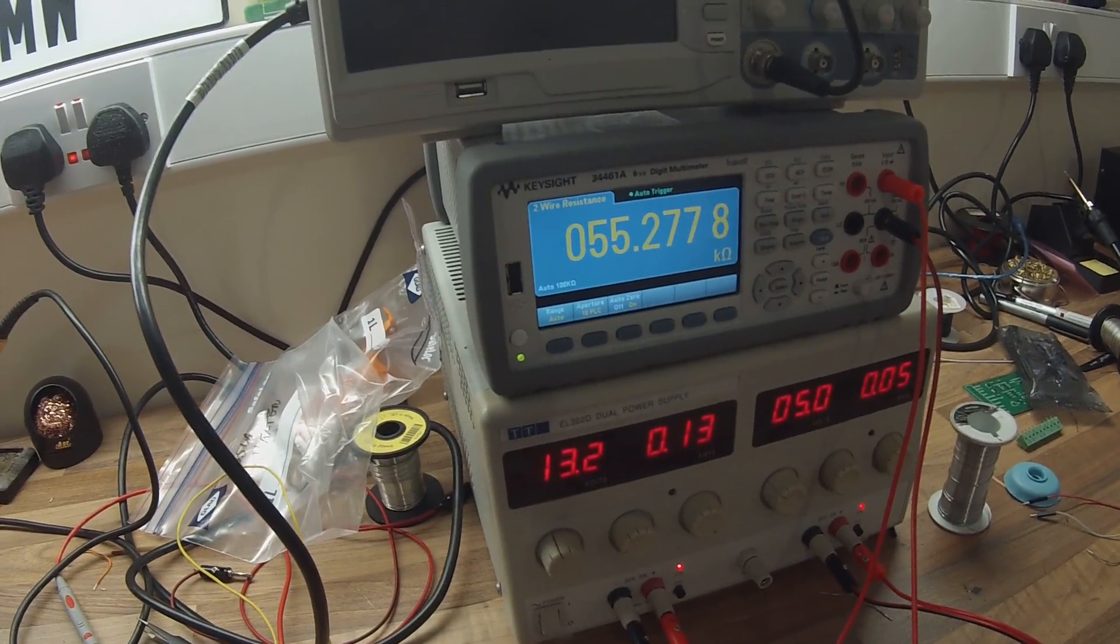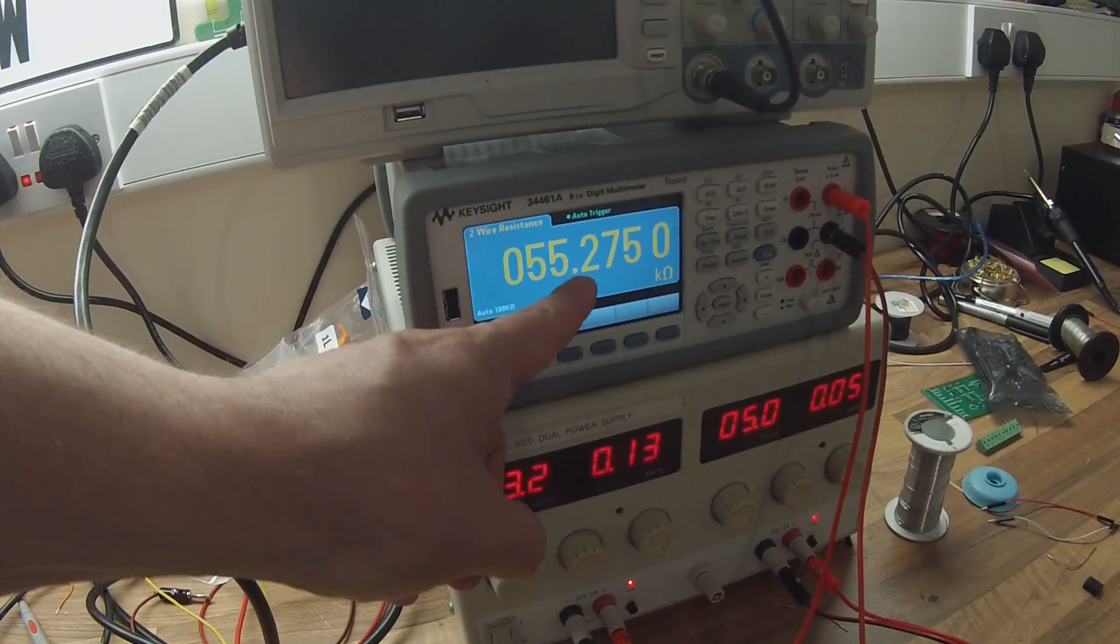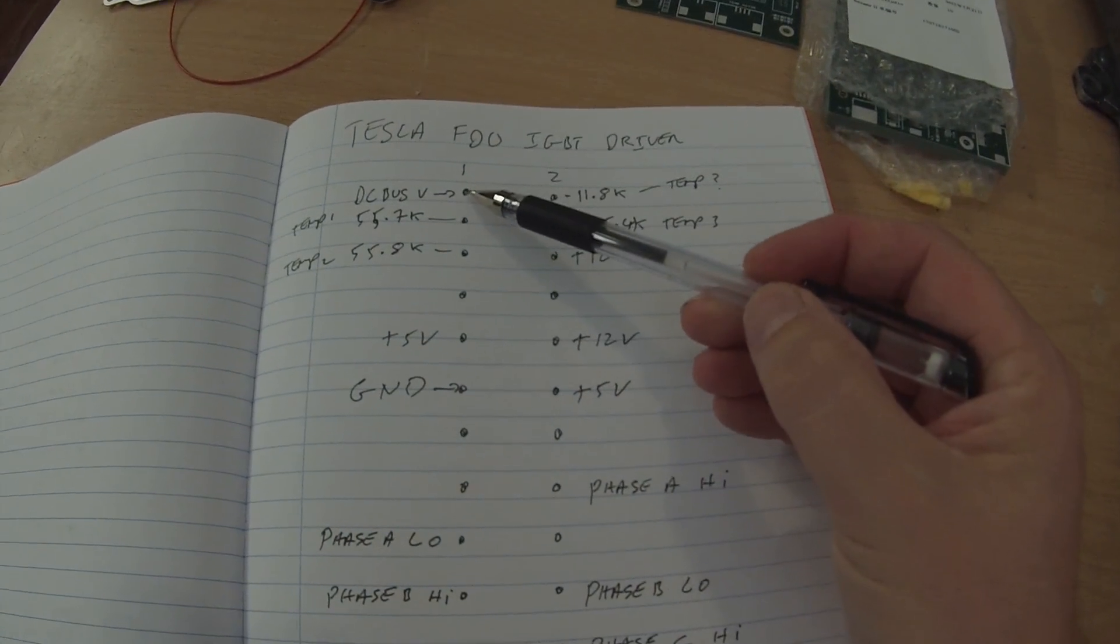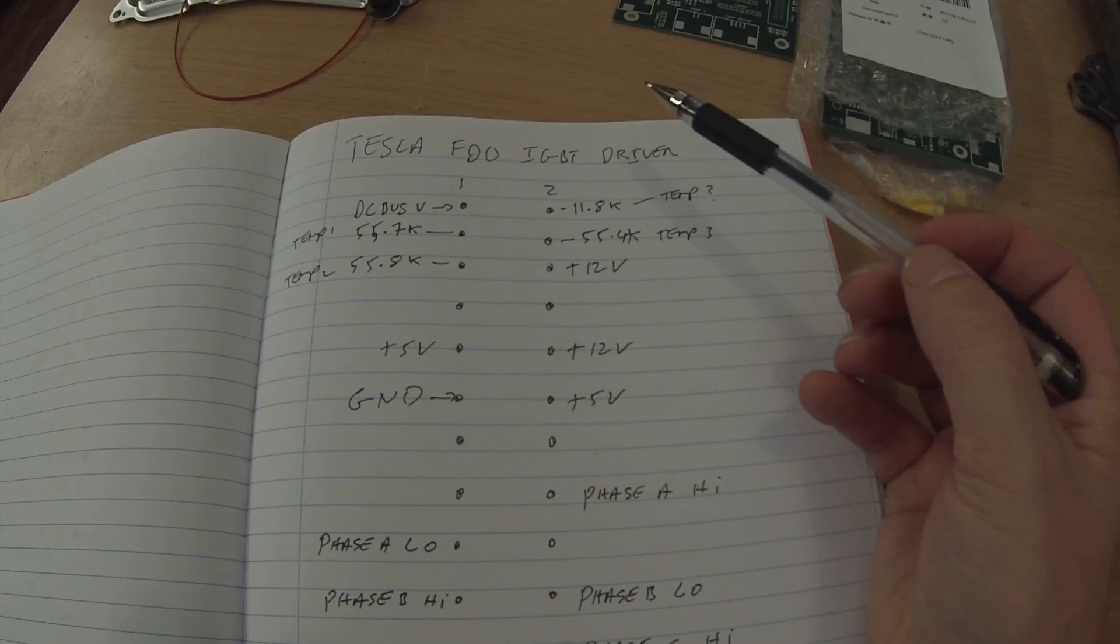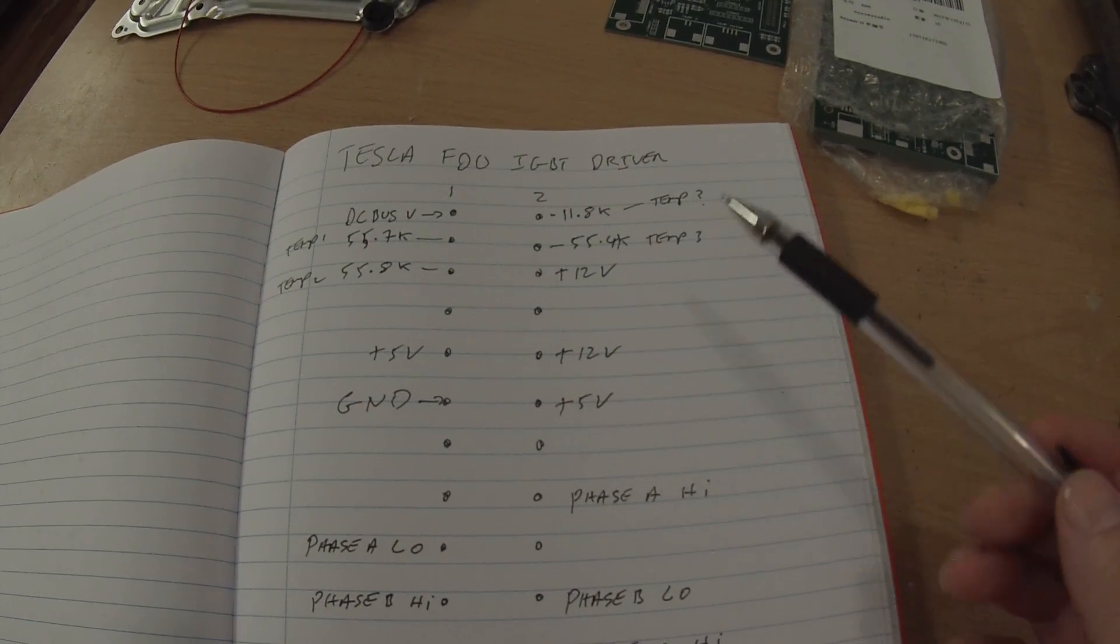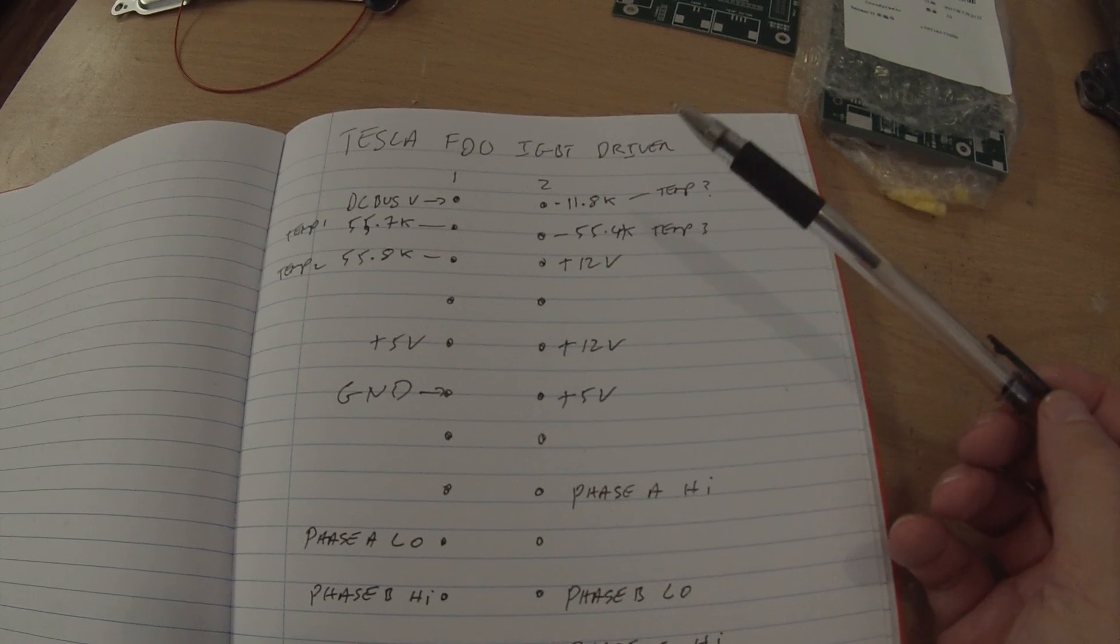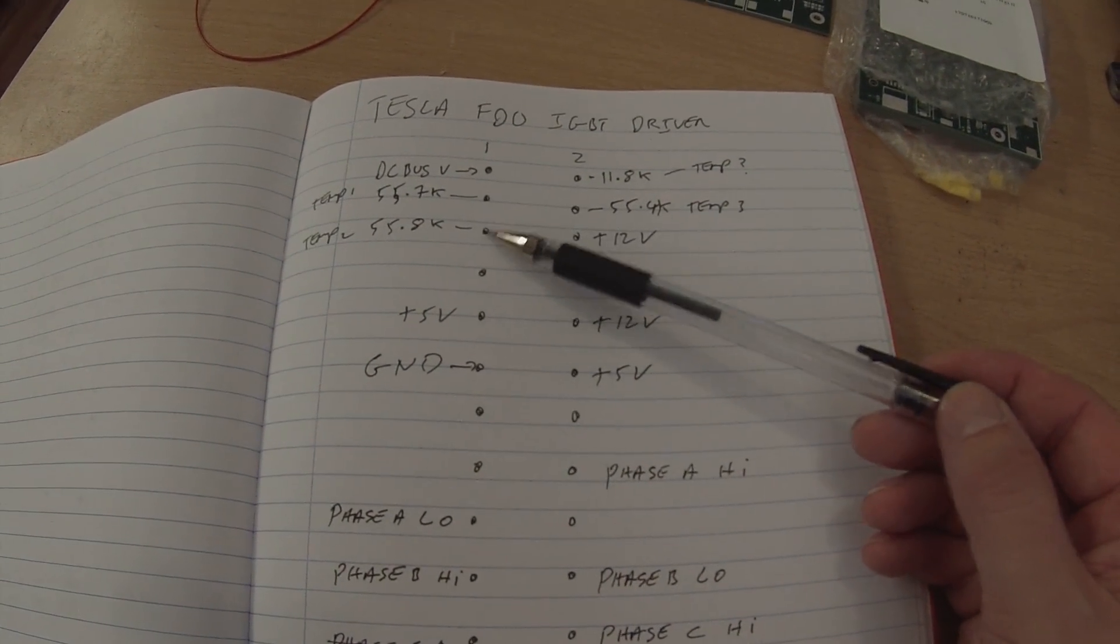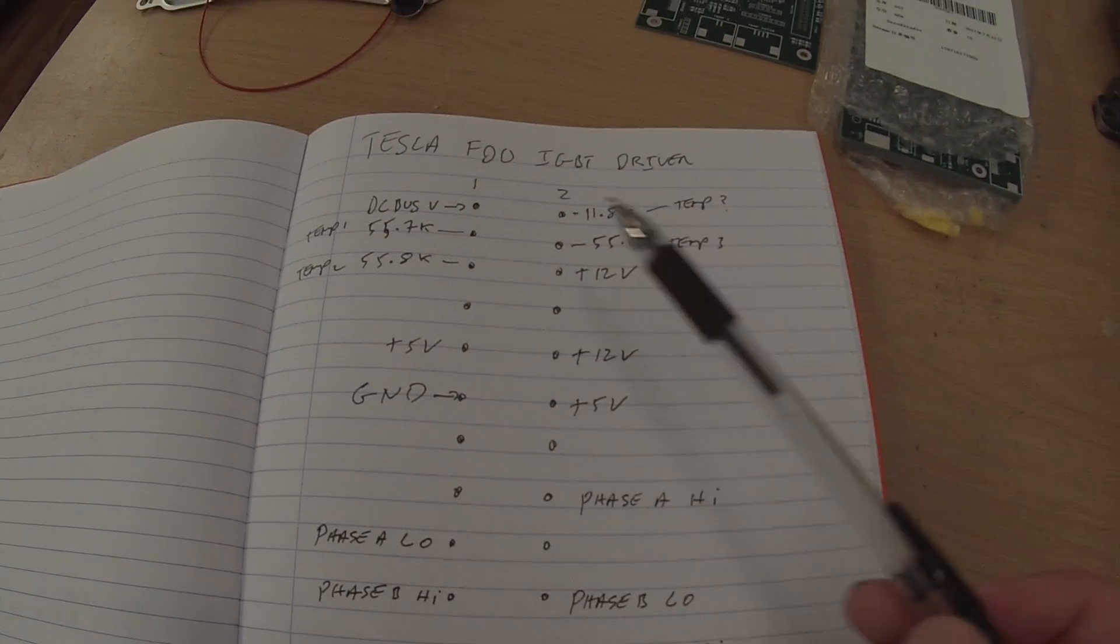You'll see that we have found three pins there with about a 55K resistance. So if we go back to our diagram here, my dodgy notes again, so pin 1 represents the DC bus voltage, and then we have these pins here. Total of four of them, but three give me broadly the same resistance. This pin, this pin, and this pin.